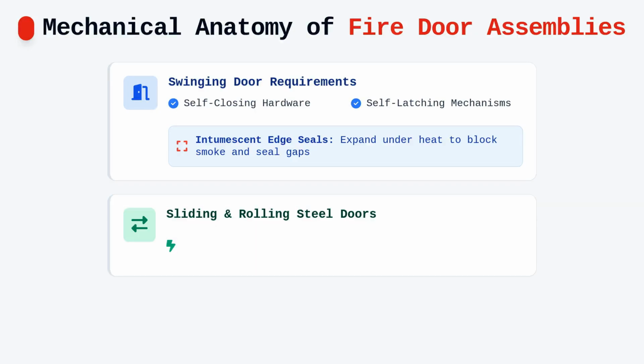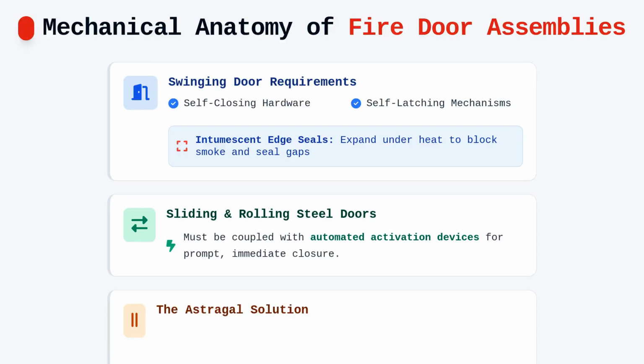For sliding or rolling steel doors, the mechanism must be coupled with devices that ensure prompt closure upon activation. Astragals are utilized on pairs of doors to cover the meeting edge, ensuring that no direct path for heat or flame exists through the center of the opening. The physical interplay between these mechanical parts is what allows a fire-rated door to behave like a monolithic wall during a thermal event.